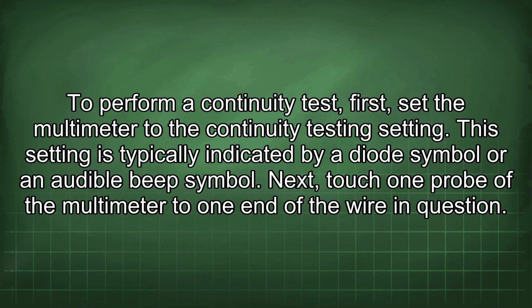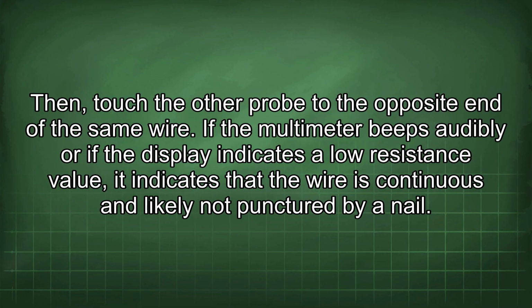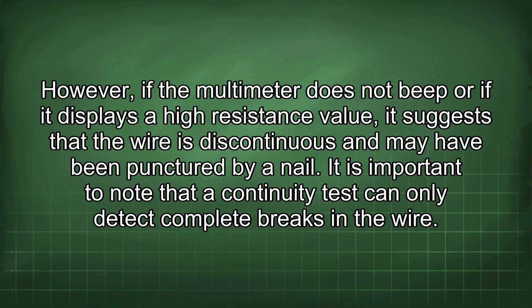To perform a continuity test, first set the multimeter to the continuity testing setting. This setting is typically indicated by a diode symbol or an audible beep symbol. Next, touch one probe of the multimeter to one end of the wire in question. Then touch the other probe to the opposite end of the same wire. If the multimeter beeps audibly or if the display indicates a low resistance value, it indicates that the wire is continuous and likely not punctured by a nail. However, if the multimeter does not beep or if it displays a high resistance value, it suggests that the wire is discontinuous and may have been punctured by a nail.